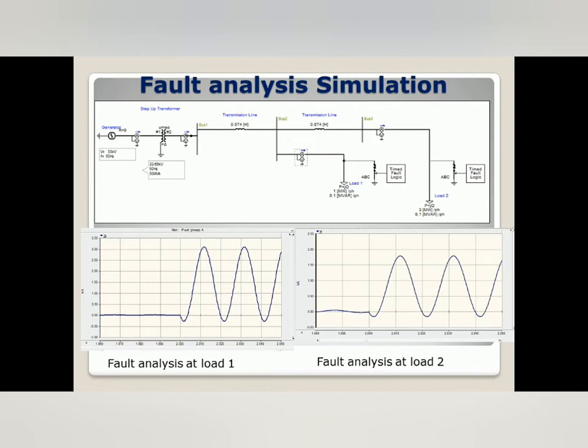By tapping the iLoad1 signal into the output channel, the result is shown in the figure. The result shows that the current spiked from the original 12.4 ampere peak to 3090 ampere peak. To get the I fault max, the simulation needs to be compared with the load 2 fault current results. At load 2, the current spiked from 37 ampere peak to 1780 ampere. The result shows that the I fault max is achieved when the fault is near the first load in the diagram.